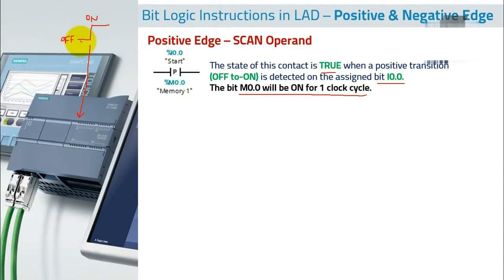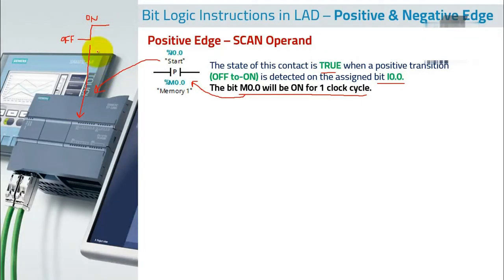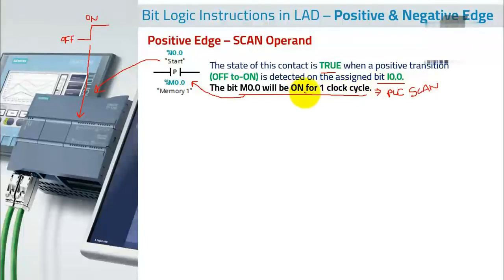If that state goes from off to on, a pulse will be detected at M0.0. This bit will be on for one clock cycle, which is typically equivalent to your PLC scan cycle. For example, if your PLC scan cycle is five milliseconds, this bit will be on for five milliseconds.